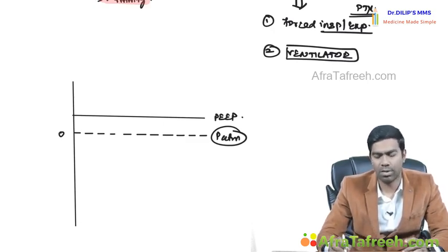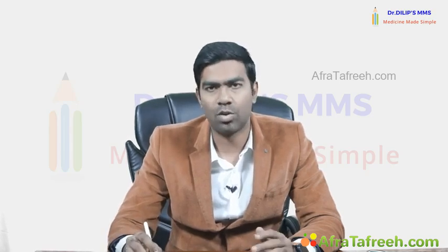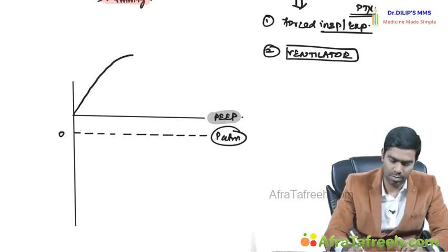At the same time, remember, this is the lowest pressure that your ventilator and the lung system can reach. You cannot go below this pressure because that is how the ventilator works. Even at end expiration, this is the minimum pressure that will be maintained. You should also remember the fact that your inspiration on a ventilator is a passive phenomenon. Even though it's a passive phenomenon, it's a forced one and a positive pressure one. So you're going to give a positive pressure breath.